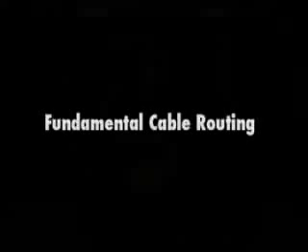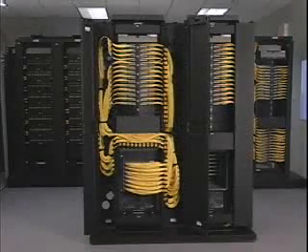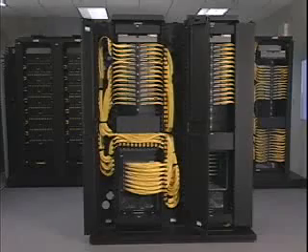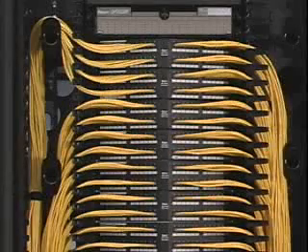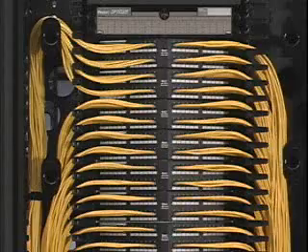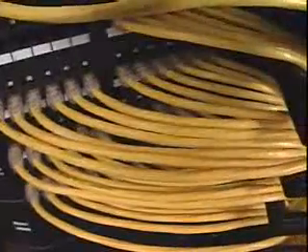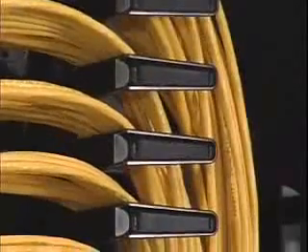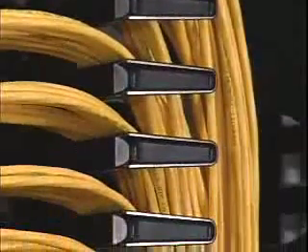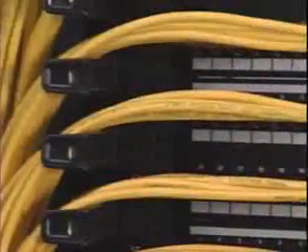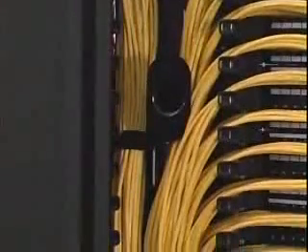Fundamental Cable Routing: After all system components have been installed, cabling can begin. Basic guidelines for patch panel routing are: patch cords are routed directly horizontally from the patch panel into the finger opening that is aligned with the patch panel rack unit. The patch runner cable management fingers have been designed to support patch cords as they transition to the vertical pathway, eliminating the need for horizontal cable managers.